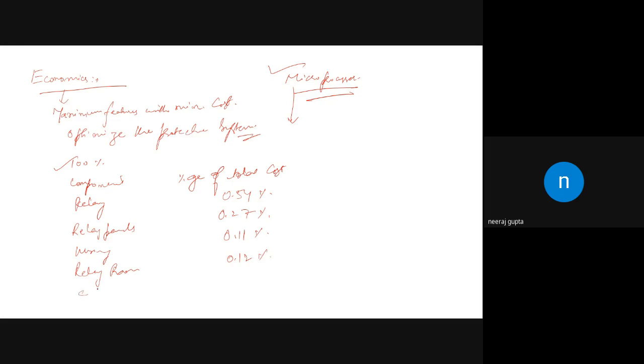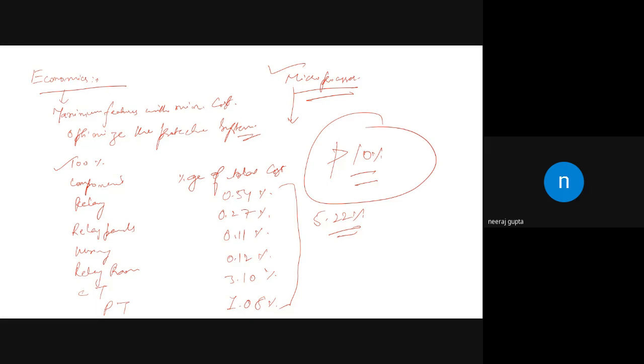And CT is 3.10%, and PT is 1.08%. If you take the total cost of this protective equipment, it is 5.22%. However, you can say 6 to 7%. The cost of the protective system will not exceed 10% of the cost of the whole equipment. So a maximum of 10% is the limit for this protective equipment. So this is about the economics.